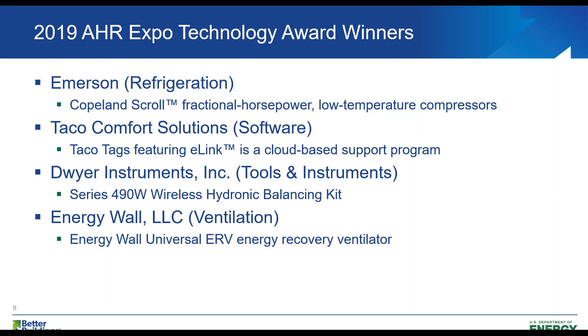The bypass is important so you can bypass the ERV and avoid the pressure penalty when you don't want to ventilate, or when you want to ventilate but not energy recover. So that's a big deal. These are solid, I think ceramic membrane ERVs, so they're very effective for latent and sensible heat recovery. Check it out—I think it's going to be great.